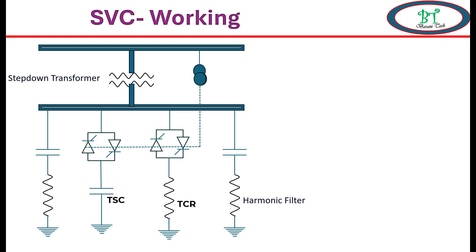Now we will see about the working of SVC. Let us consider there is a sudden loss in load. Due to this, the power factor leads during this time. Then the TCR will get switched on and reduce the power factor to normal. Once the power factor comes to normal, the TCR will get turned off.